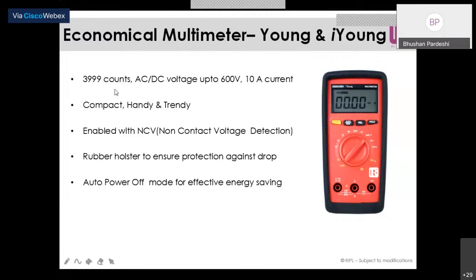Now why are these counts and digits important? Because when my count is 3999, I cannot show a reading of 2000 on the multimeter. So if I'm measuring ohms, it will not show me 2000 ohms directly - it will show me 2 kilo-ohms, like 2.00 kilo-ohms. It will not show me 2000 ohms as such. So the resolution of the meter depends on the number of counts and digits. That's why counts and digits are an important factor in any multimeter - the more the number of counts and digits, the better resolution you get.